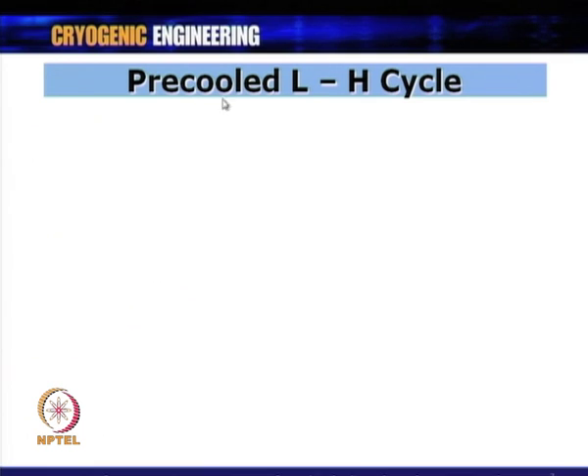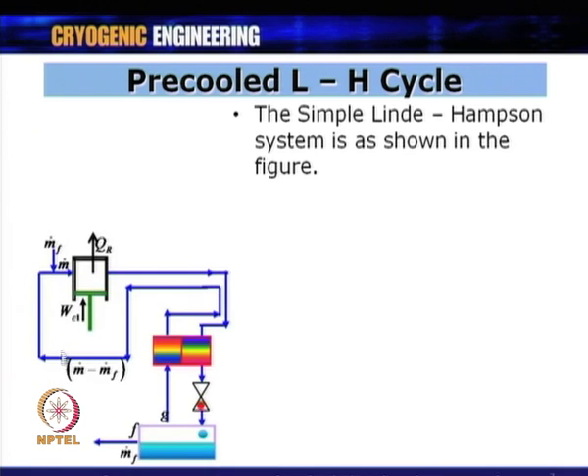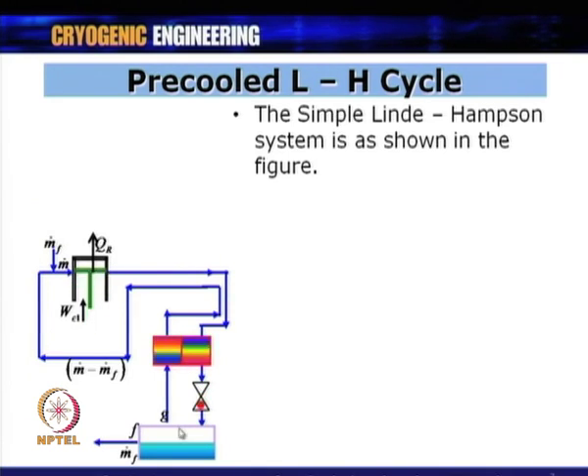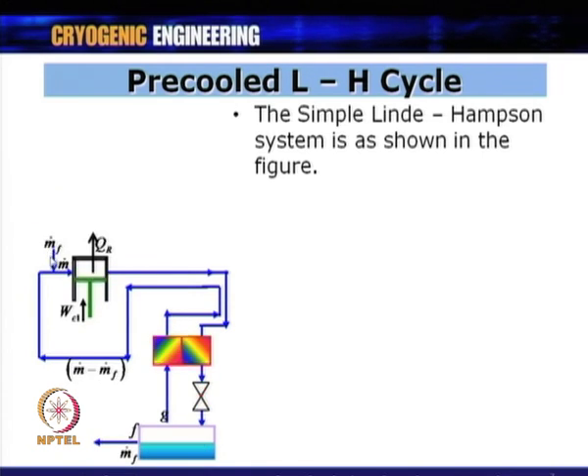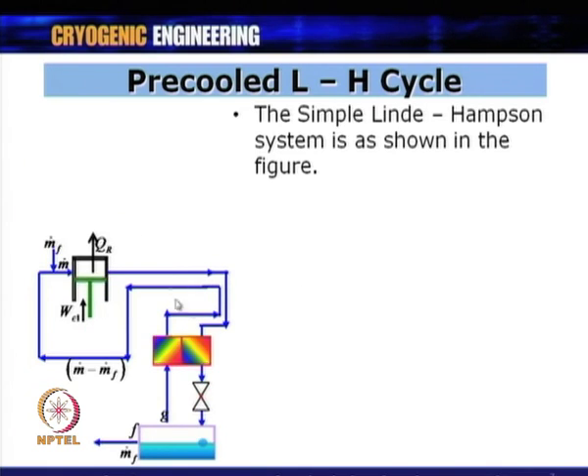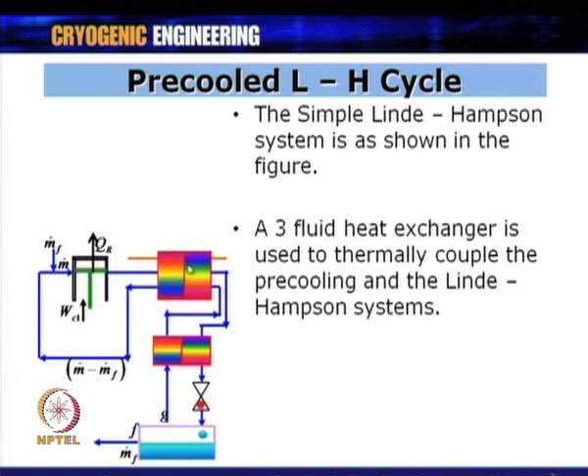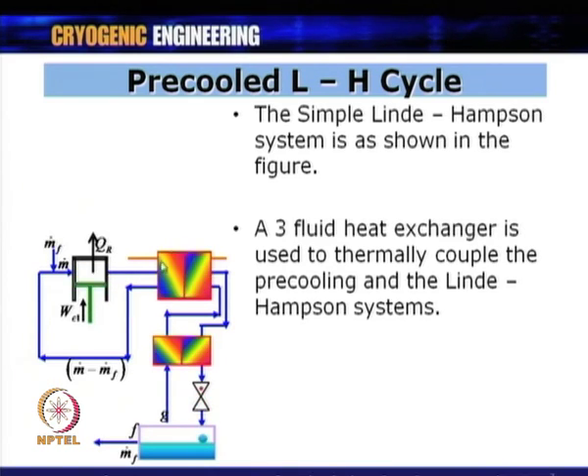The simple Linde-Hampson system has a compressor, then the compressed gas passes through a heat exchanger, expands to produce liquid m_dot_f, and the return gas pre-cools the incoming high-pressure gas before returning to the compressor. In the pre-cooled system, in addition to this heat exchanger, a pre-cooling heat exchanger is added where the high-pressure gas leaving the compressor is pre-cooled by another refrigerant passing through it at a much lower temperature.